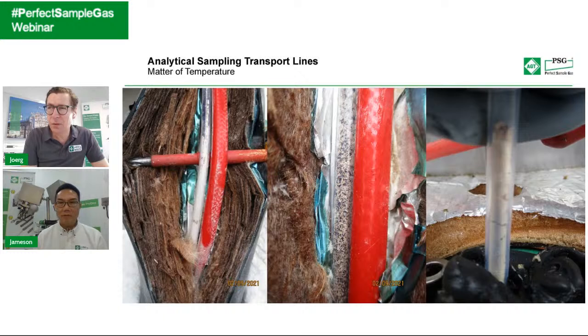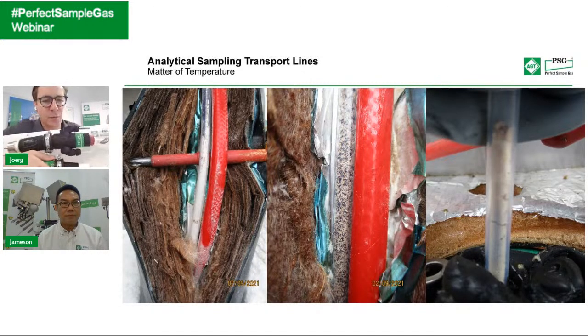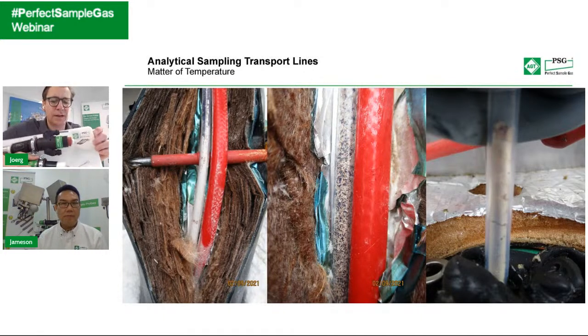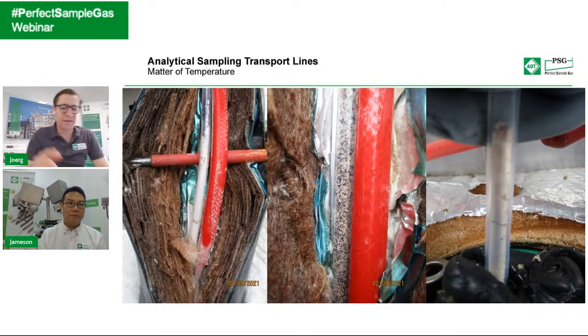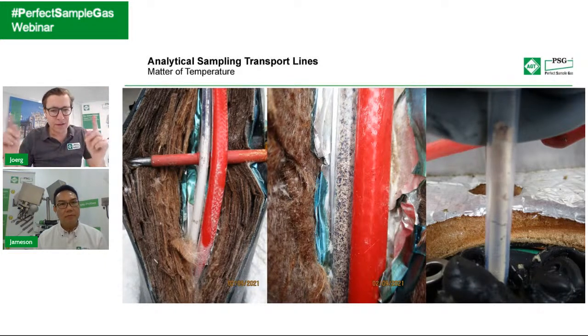So Jameson, maybe quick fix is difficult there, but whenever a customer contacts us with problems in the heated sample line, we recommend to use an infrared camera and really try to measure the temperature of the heated sample line. Depending on what technology you use, with a fixed resistance heater, you have the situation that it's either working or not. So if this is not working, you will see immediately. But you might have a zone heater cut to length, and if a zone is not working, you will not see that in the power consumption. So in this case, you would need an infrared camera in order to check if the temperature is still there.